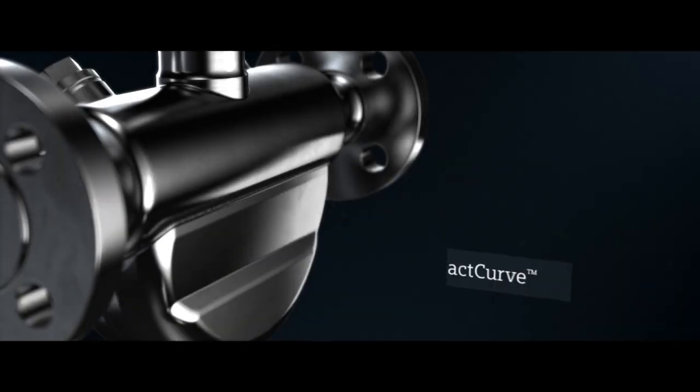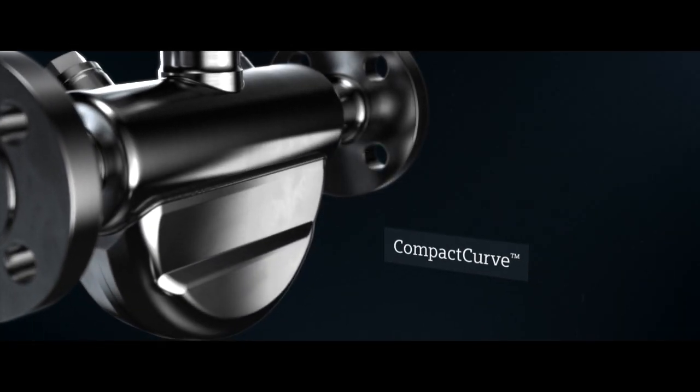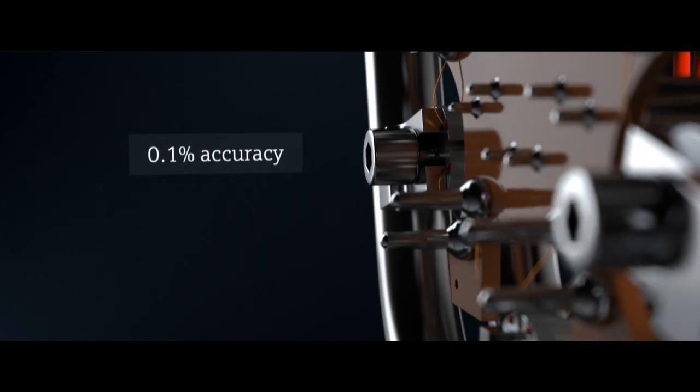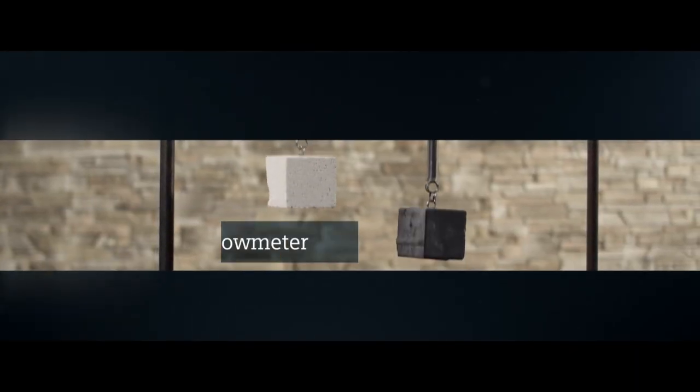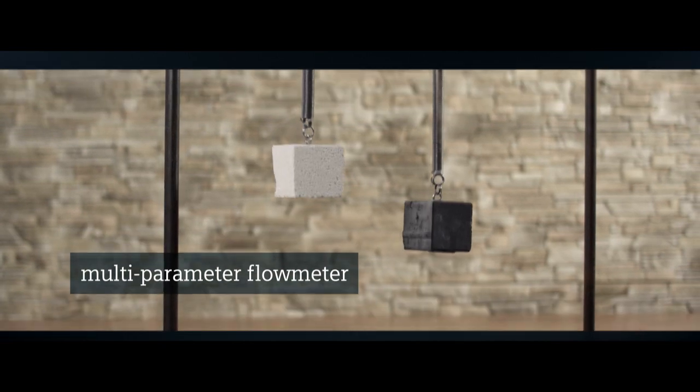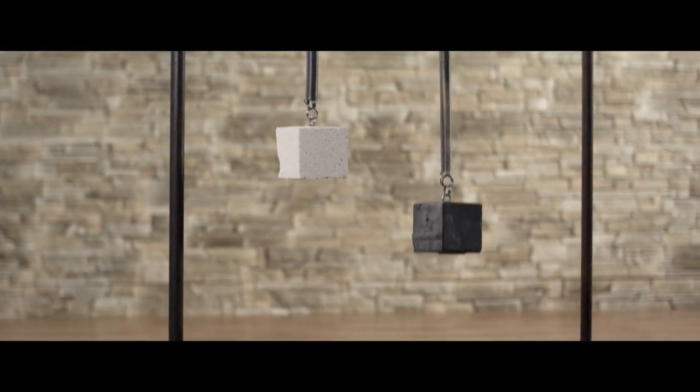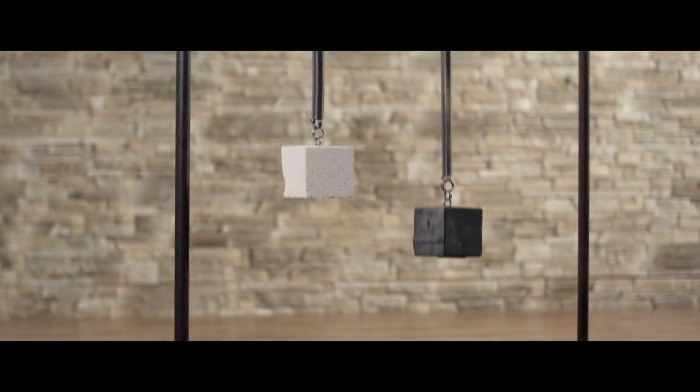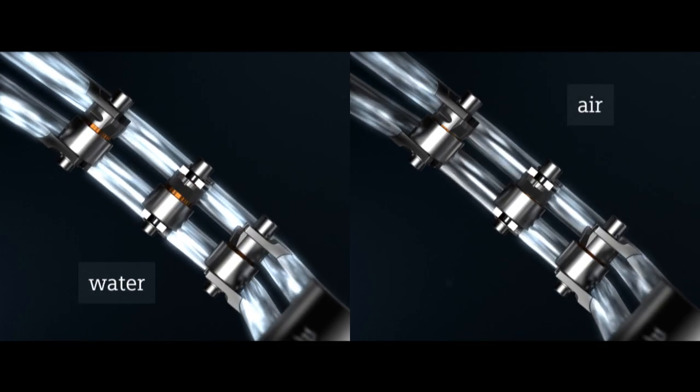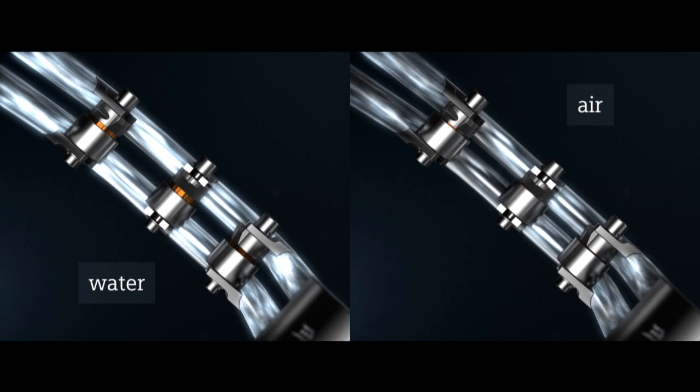A multi-parameter flow meter with maximum reliability. In addition to the mass, it determines the density of a medium. Denser media have lower frequencies. Put otherwise, water oscillates at a lower frequency than air.